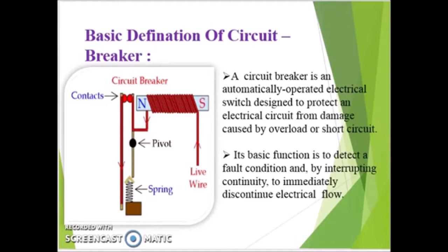You can see in the diagram there is a spring, and a circuit breaker consists of two contacts. The first is a fixed contact and the other one is a moving contact. Also there is a coil and there is a pivot. As soon as the coil is energized, the fixed and moving contacts move apart. So the moving contact will move apart from the fixed contact.